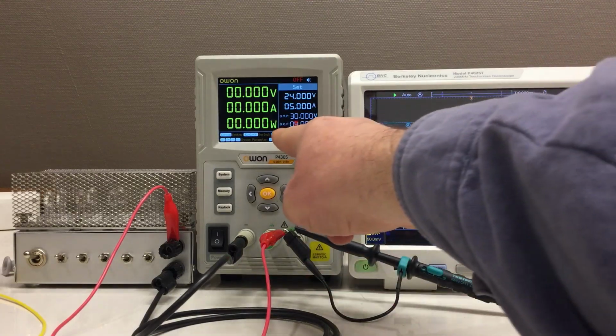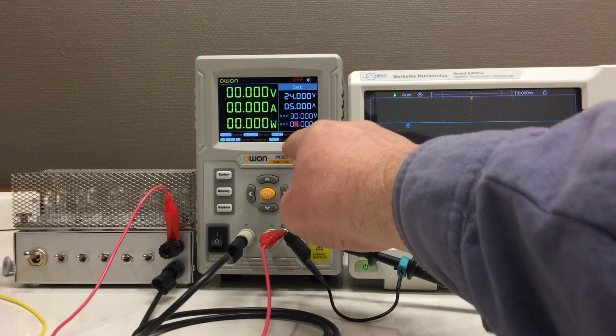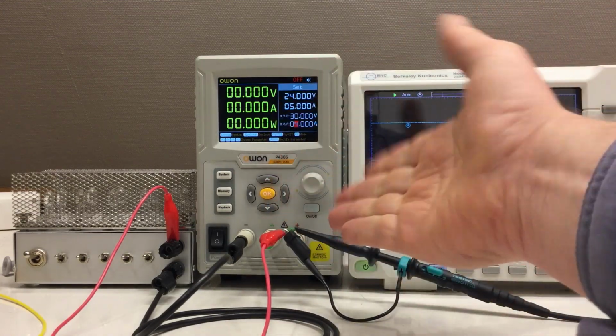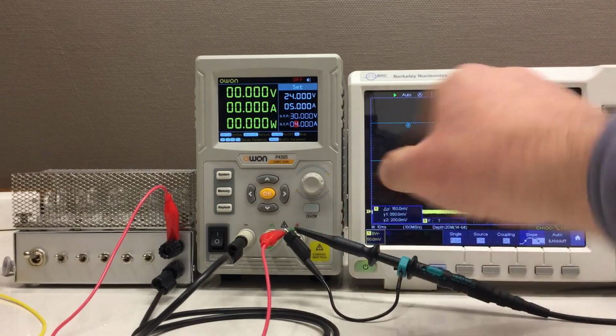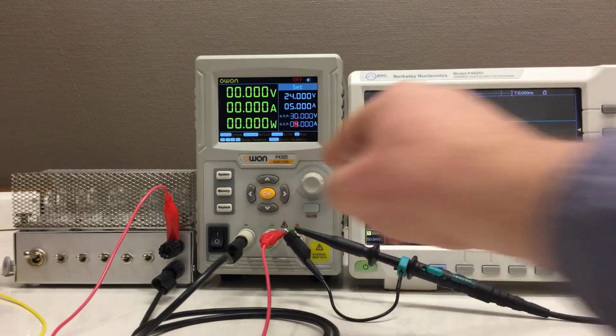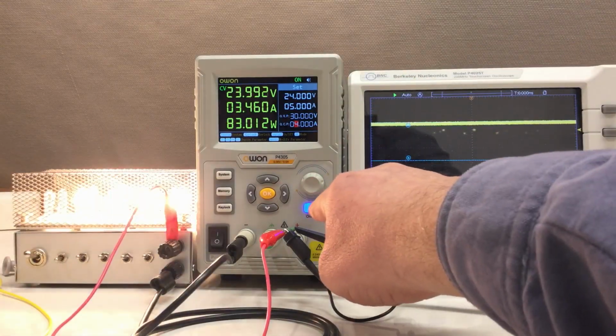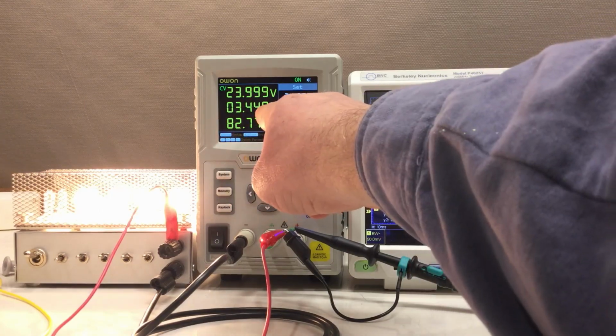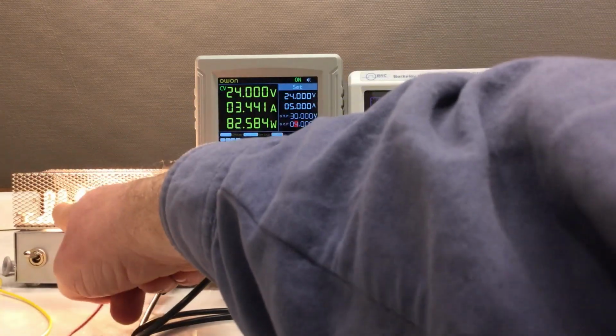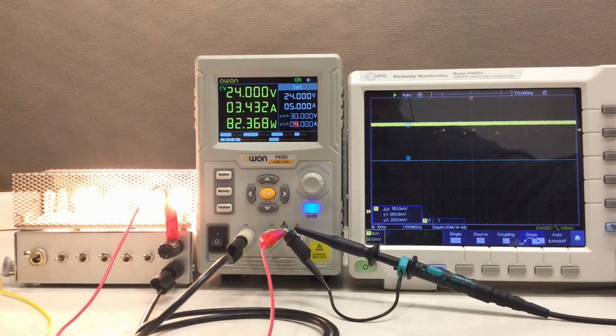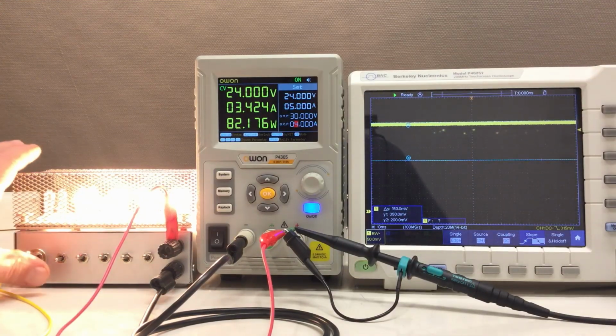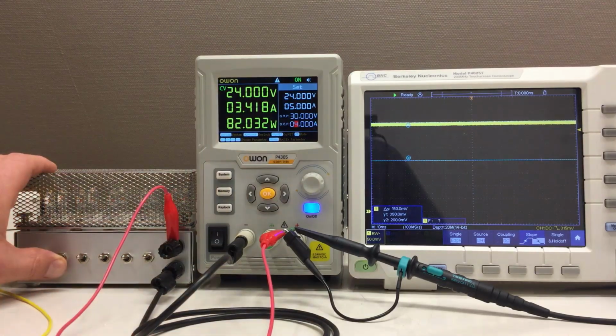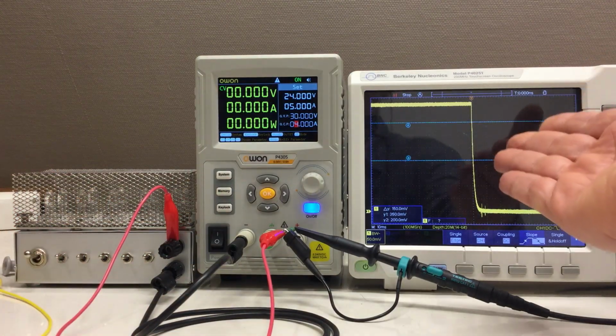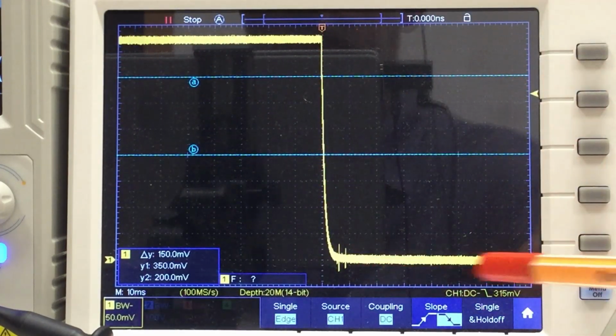There are 2 more transients we have to look at, and that is the switch off for overcurrent protection and overvoltage protection. Since I've already set up the whole thing for current measurement, I set the overcurrent protection at 4 amps. And if I switch on, we are drawing 3.5 amps, and 1 row of halogen bulbs is off. I go to single mode and then I switch them on, and that looks absolutely okay.